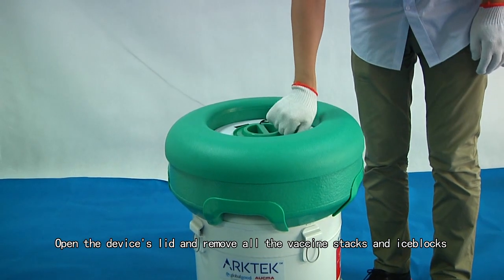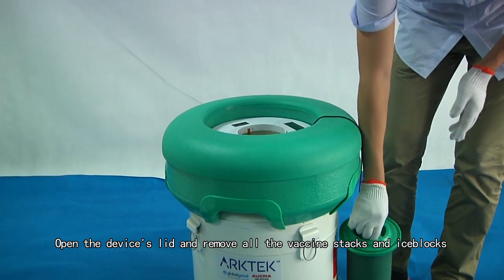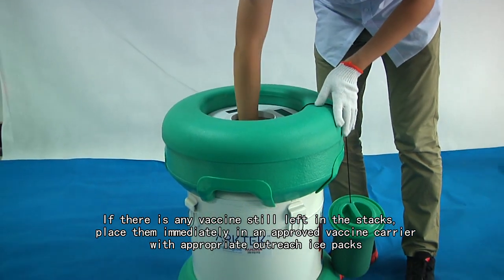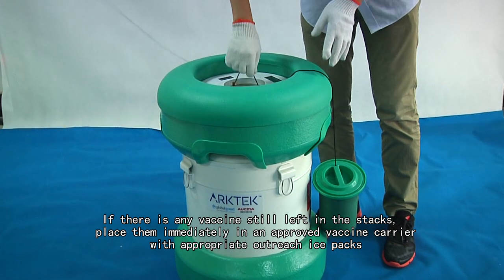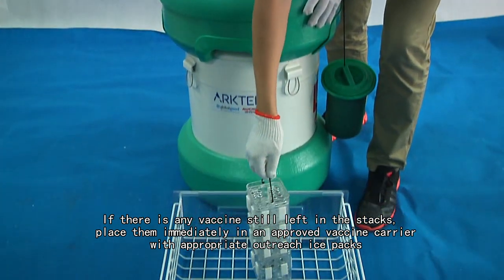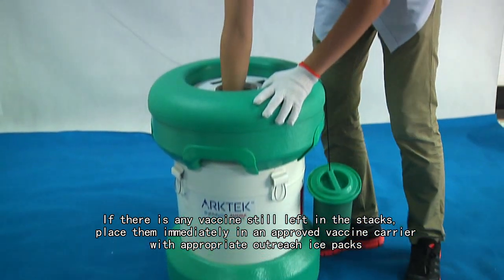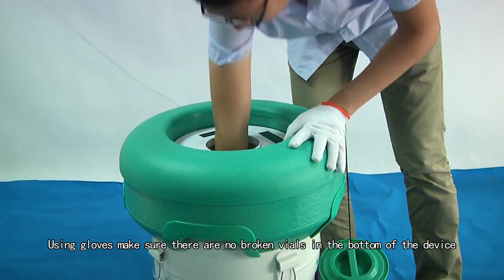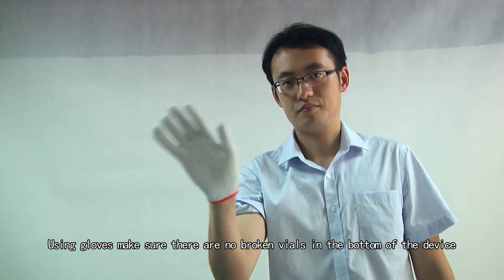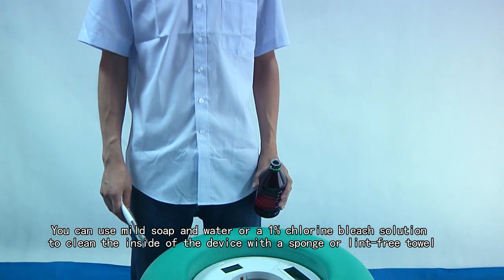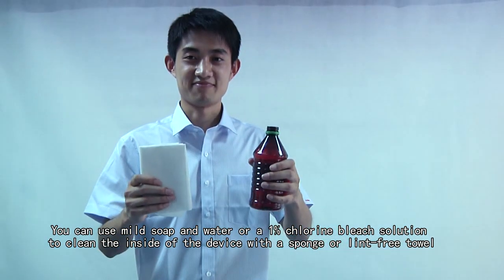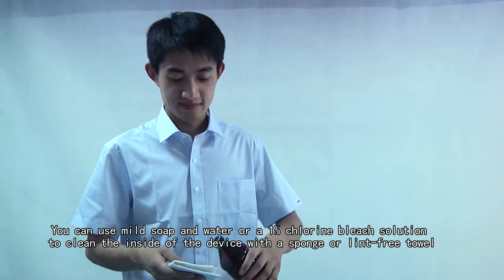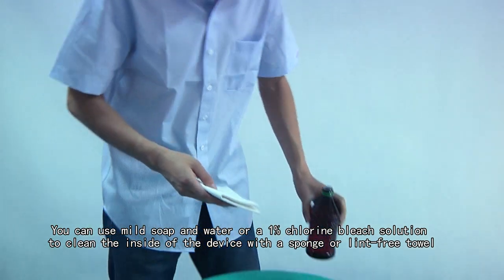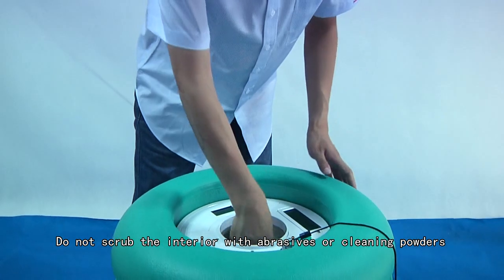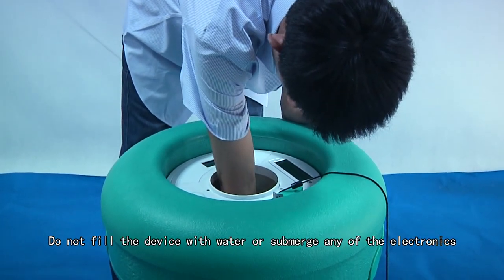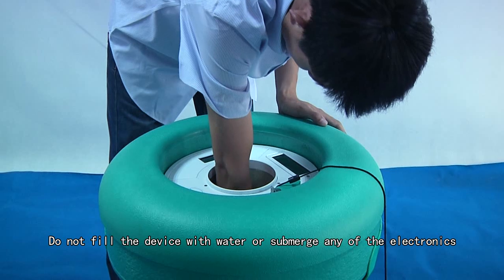Open the device's lid and remove all the vaccine stacks and ice blocks. If there are any vaccines still left in the stacks, place them immediately in an approved vaccine carrier with appropriate outreach ice packs. Using gloves, make sure there are no broken vials in the bottom of the device. You can use mild soap and water or a 1% chlorine bleach solution to clean the inside of the device with a sponge or lint-free towel. Do not scrub the interior with abrasives or cleaning powders. Do not fill the device with water or submerge any of the electronics.